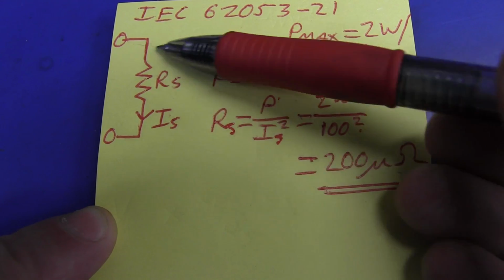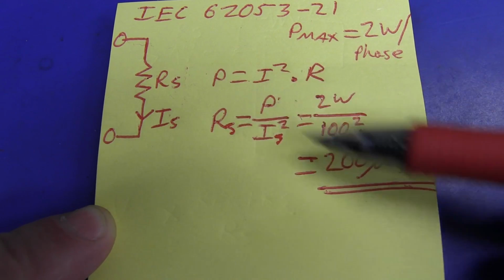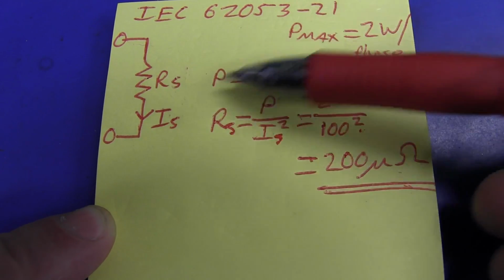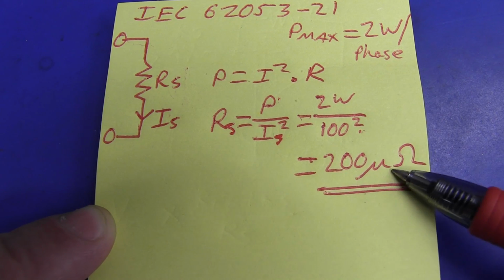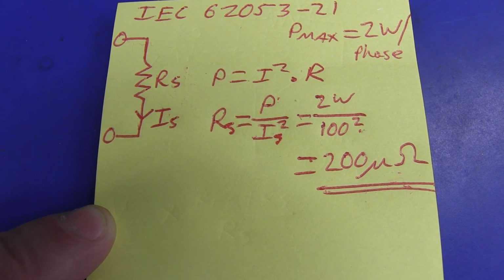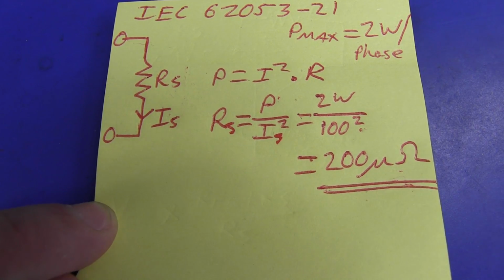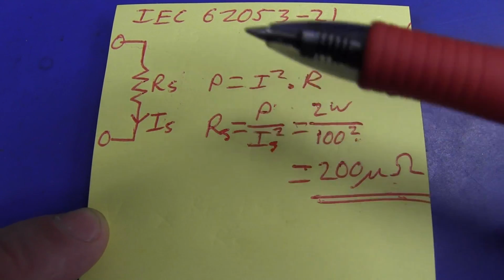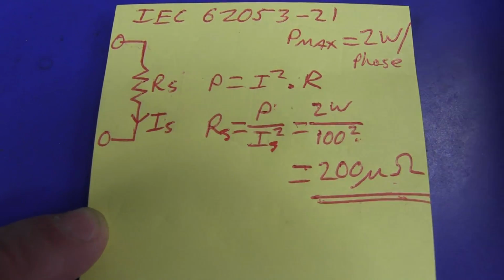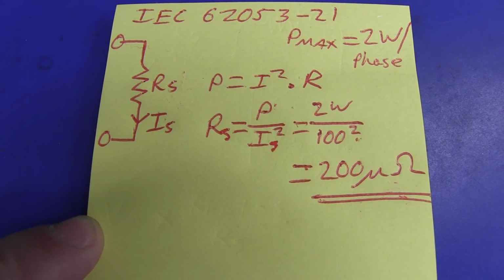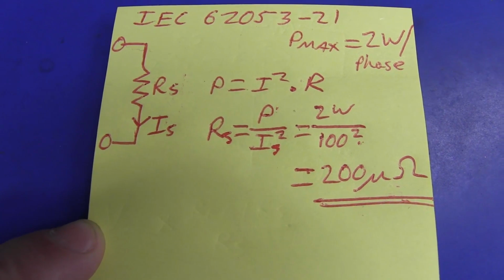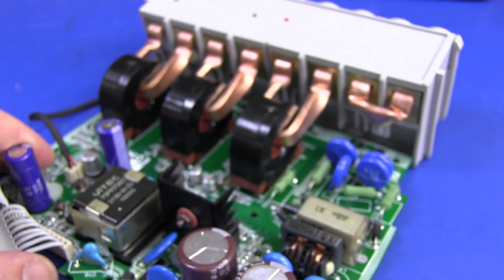At low values of current, instead of say 100 amps, if your house is only drawing say 1 amp on that phase, what's the voltage drop across that shunt resistor? Well, do the math, it's going to be about 200 microvolts. We're talking very small voltages at very small currents, and that becomes a pain to measure, let alone 100 milliamps or 50 milliamps. So what they've done is use these current transformers instead of a traditional current shunt resistor.